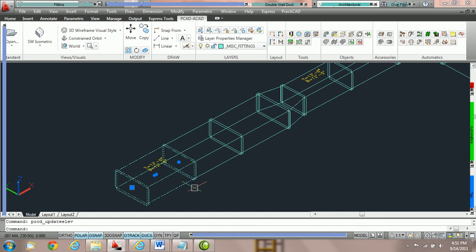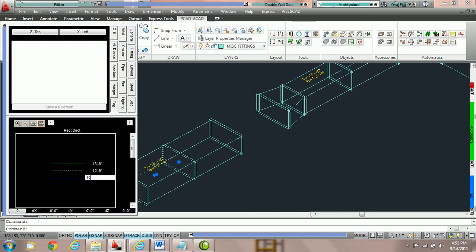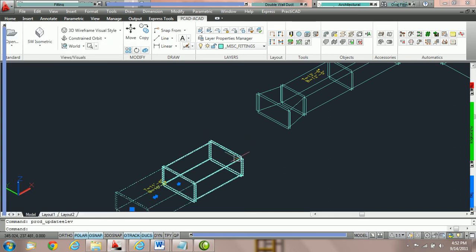Now if we wanted just 1 or 2 fittings to edit or move an elevation and not carry the rest of the duct line, we must break the duct line. For example, if we want to just move up fitting 1 and fitting 2 and not the third fitting, we would actually delete the third fitting. Then we click at the beginning of the duct line we want to change, and make the change, let's say back down to 10 foot. Then we'd of course use an auto route or a single to attach the duct line, but the idea is we've only moved the specific section of duct we want. If it's connected, it's going to edit all the way forward or backwards in the duct line.